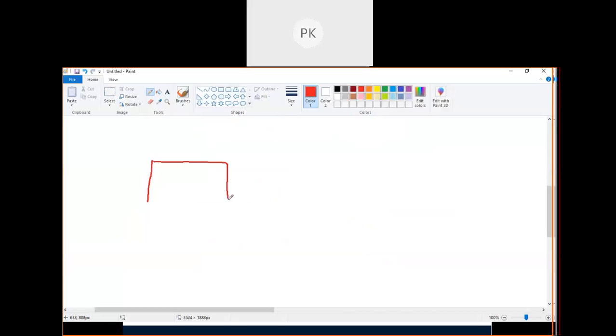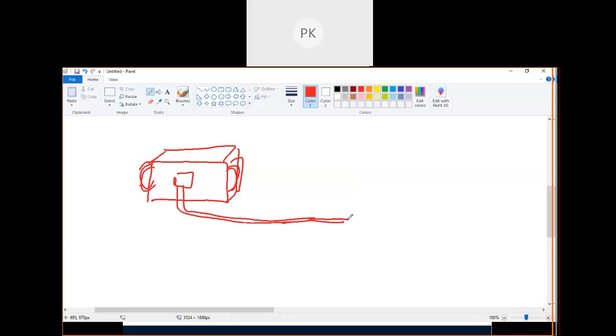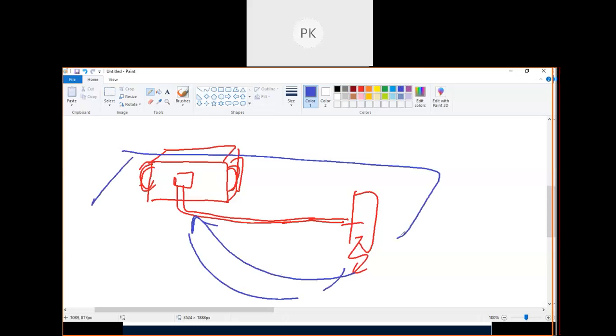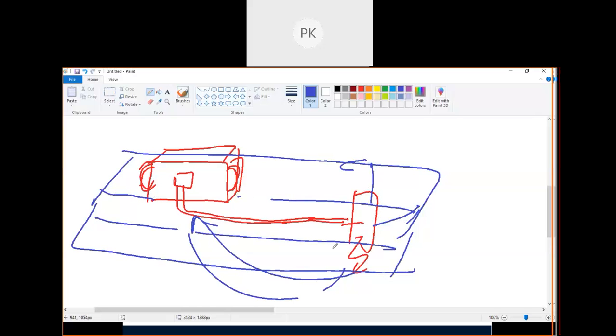Now here you have a transformer, which is supplying power to all the equipment. Whenever there is a fault somewhere in this equipment, fault current will flow back to the transformer neutral. You may have a large earth grid, so some fault current will flow here, some will flow here. There will be a number of different paths through which the fault current will flow.